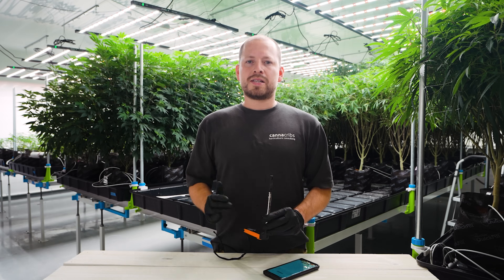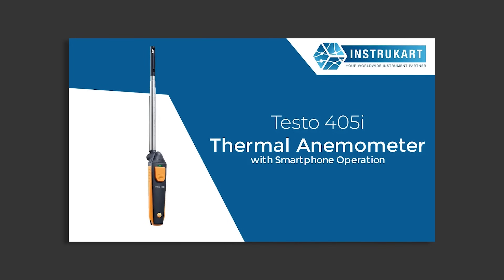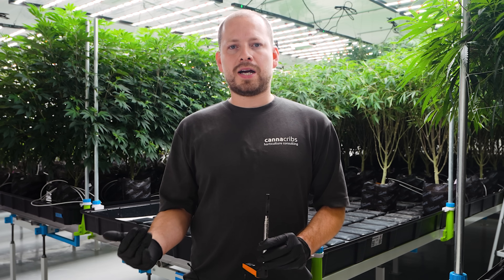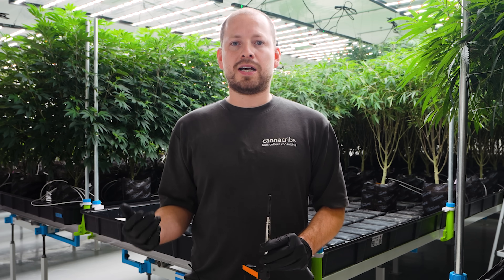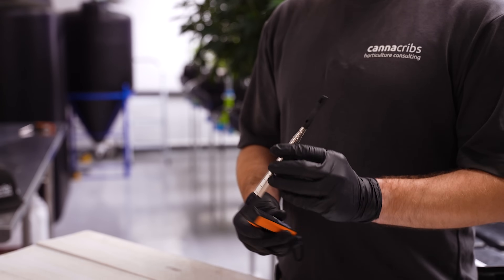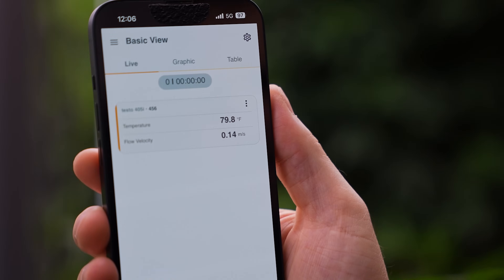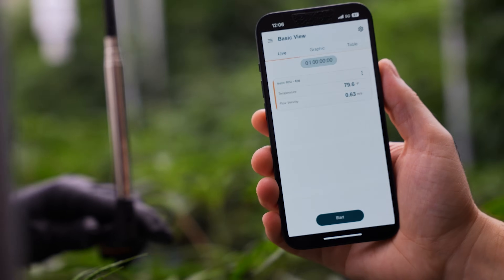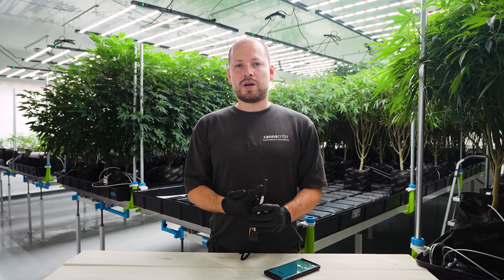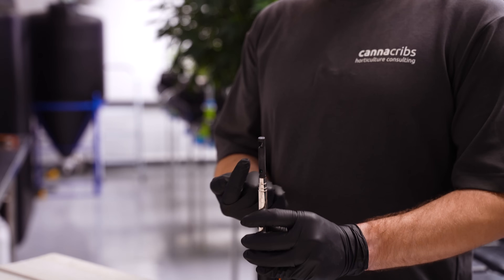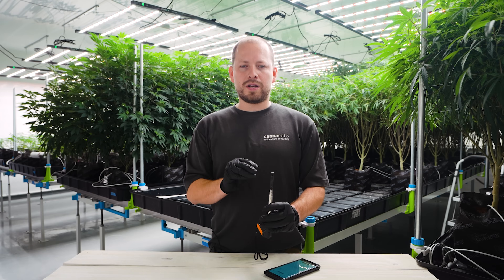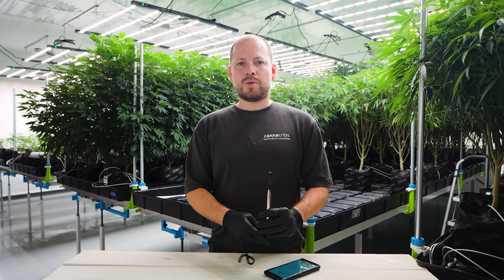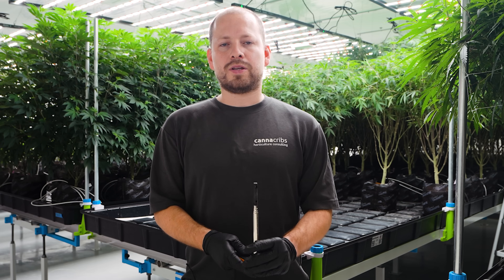So how do we measure airflow? The sensor that we like to use the most is the hot wire anemometer because it gives us the highest accuracy at even low airflow levels. Here I have a Testo 405i connected to my phone. There are different types of anemometers to measure airflow — you may have seen the vane type anemometer with a fan. However, this one here is a hot wire anemometer. The way it works is that it heats up the wire and the wind cools down the wire so that you can see the airflow level.